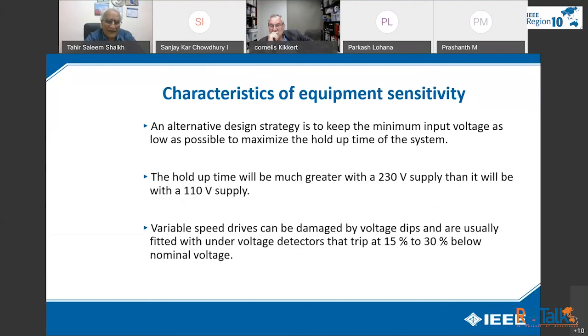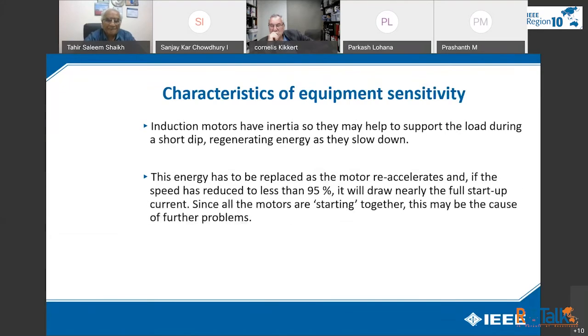Variable speed drives can be damaged by voltage dips and are usually fitted with undervoltage detectors that trip at 15 to 30% below nominal voltage. Induction motors have inertia, so they may help to support the load during a short dip, regenerating energy as they slow down. They become a generator. This energy has to be replaced as the motor re-accelerates, and if the speed is reduced to less than 95%, it will draw nearly the full startup current. Since all the motors are starting together, this may be the cause of further problems.